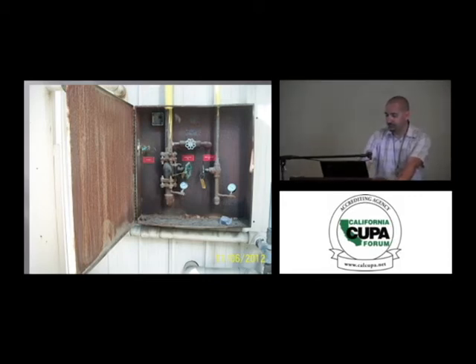Now that's done automatically. The new code is we have a pressure transducer and we operate an automatic valve. Pressure gets too high on the high side, we dump it to the low side. Yeah, so now that's done automatically. And these are not required by code anymore, the emergency or fireman's control box.